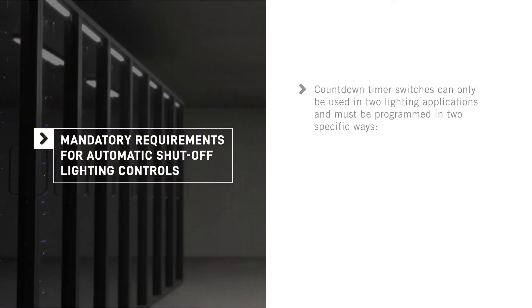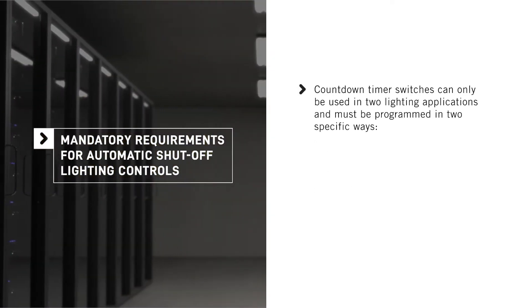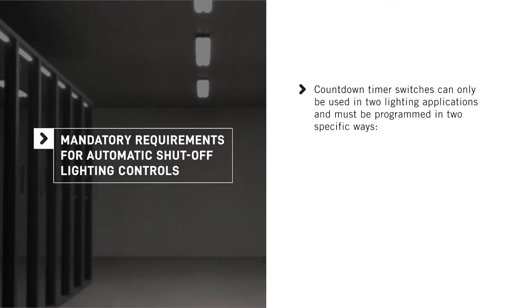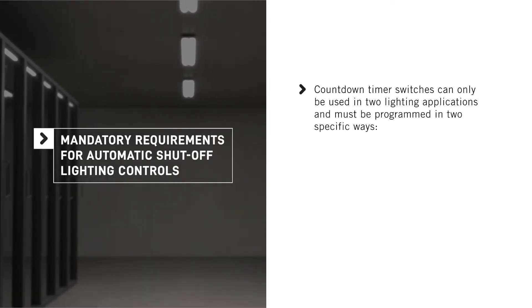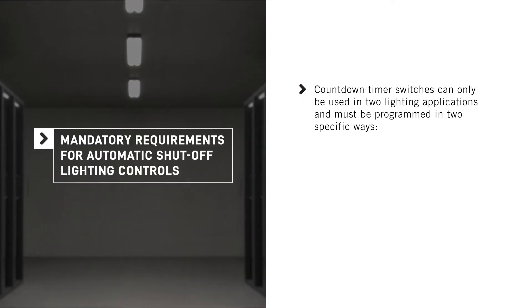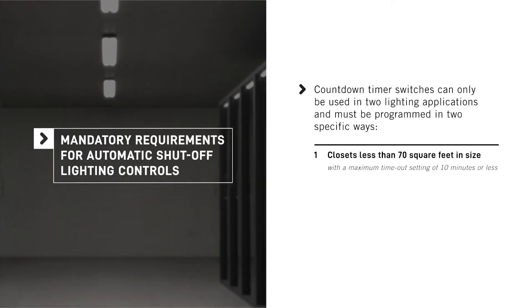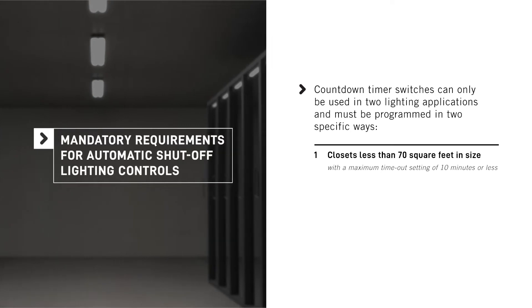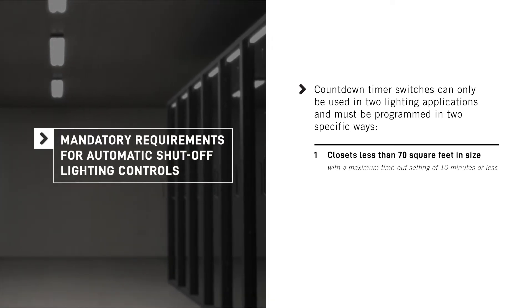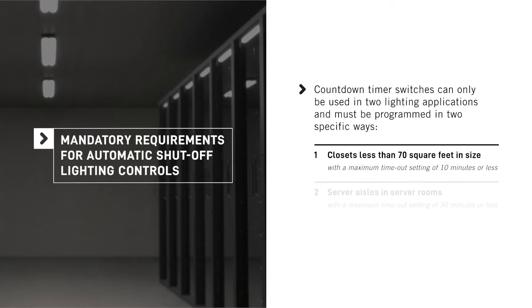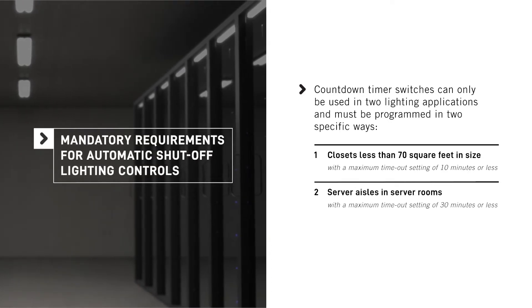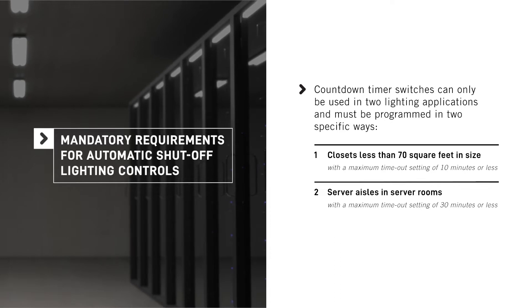A simple type of shutoff control is a countdown timer switch. Under the Energy Code, these devices can only be used in two lighting applications: closets less than 70 square feet in size with a maximum timeout setting of 10 minutes or less, and server aisles in server rooms with a maximum timeout setting of 30 minutes or less.